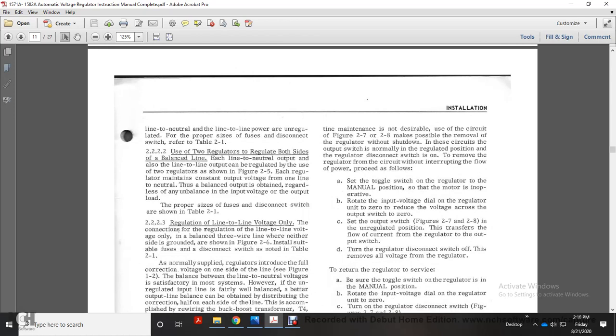Set the toggle switch of the regulator to the manual position. Check that the motor is inoperative. Rotate the input voltage dial of the regulator to 0 to reduce the voltage across the output switch to 0. Set the output switch, Figure 2.7 or 2.8, to the unregulated position to transfer the flow of the current from the regulator to the output switch. Turn the regulator disconnect switch off.